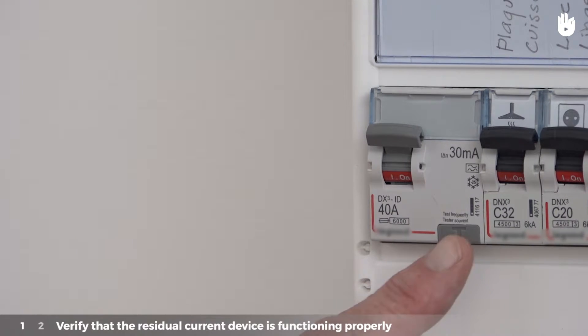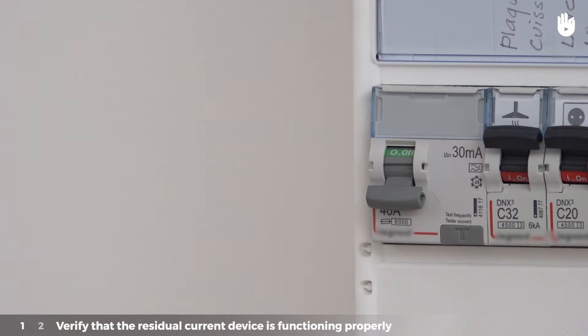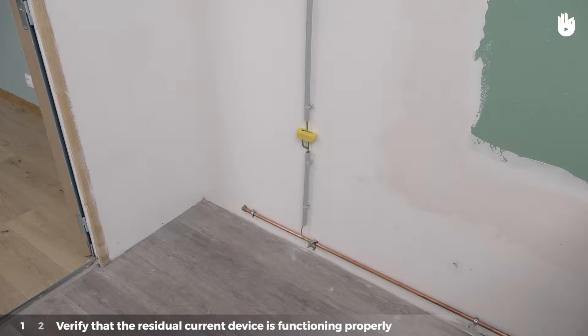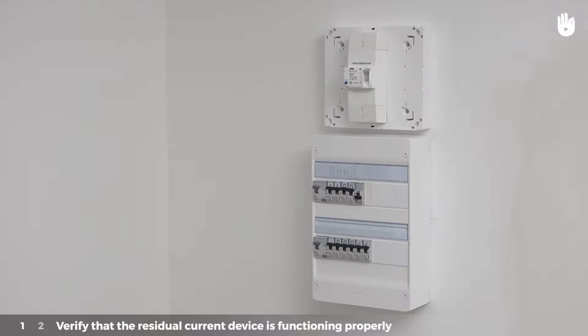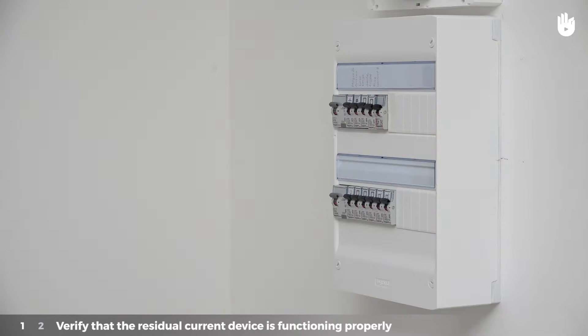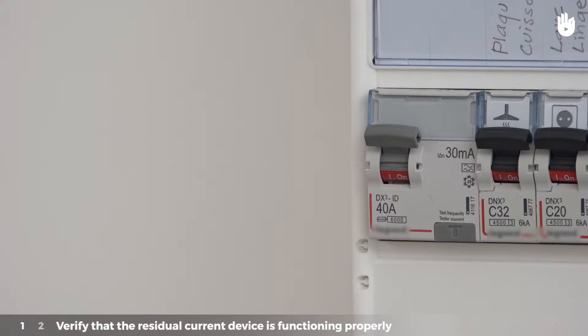Step 1: Verify that the residual current device is functioning properly. The residual current device is a system that compares the incoming current and the outgoing current. If they vary, the system will find that there is a current leak inside the appliance and the residual current circuit breaker will be triggered, cutting off the current. This is called tripping the circuit breaker.